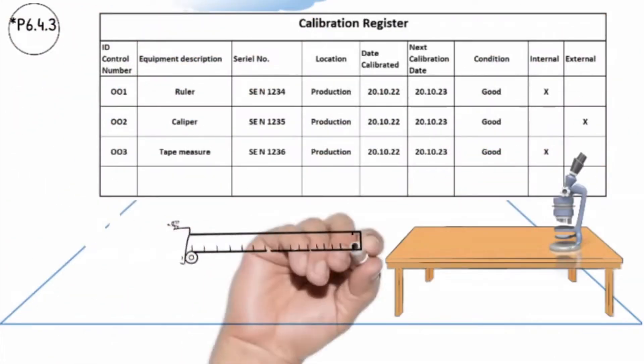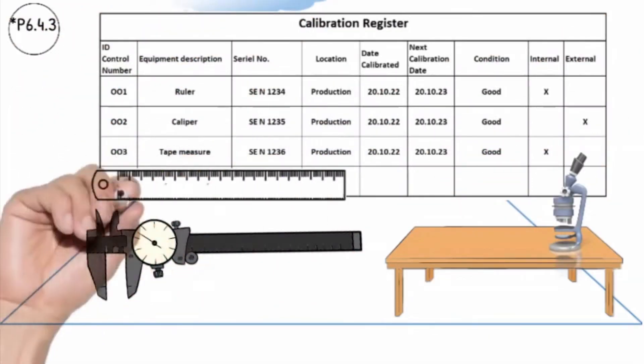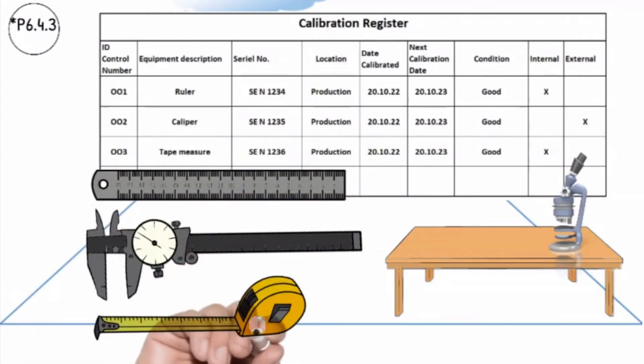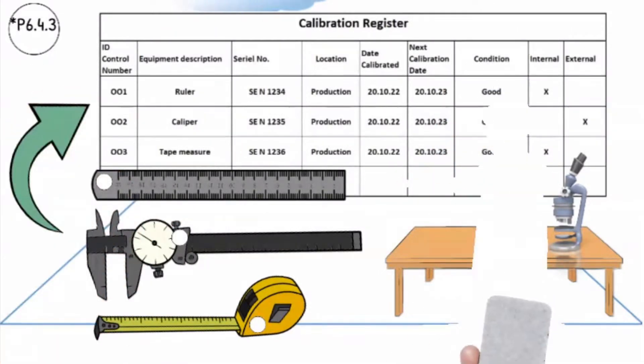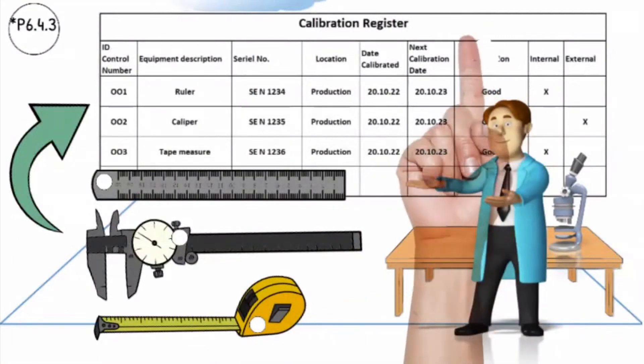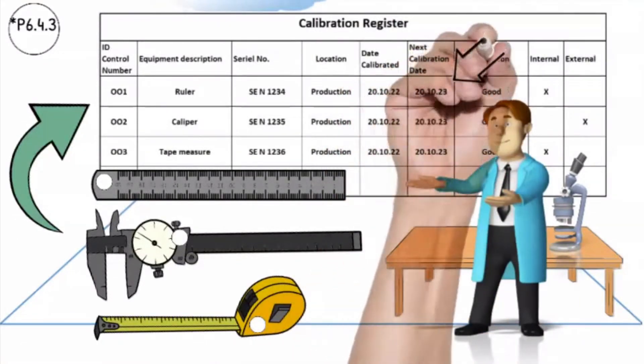All the measuring and test equipment in production is controlled and calibrated. Each measuring and test equipment is identified with a unique number, the calibration status, and included in the calibration register. The calibration technician must ensure that the equipment is recalibrated according to the frequency in the calibration register.